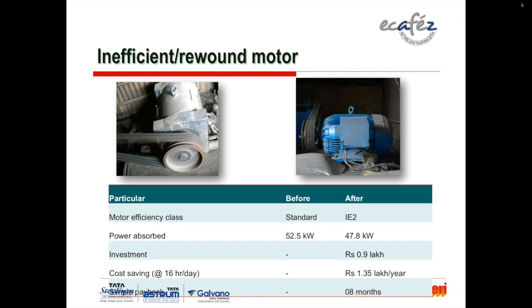In fact, we recommended an IE3 motor, which is more expensive. The investment would have been about 1.5 lakhs for the IE3 motor, almost 1.5 times that of the IE2 motor. But the payback would be 2 to 3 years. However, the unit decided to go for the IE2 motor in this particular case.